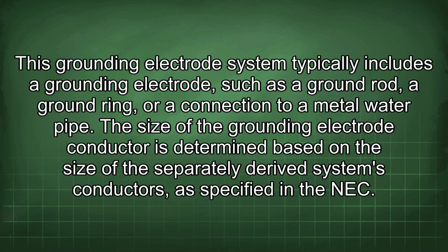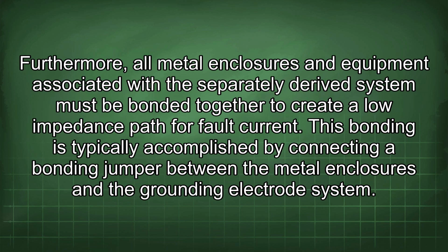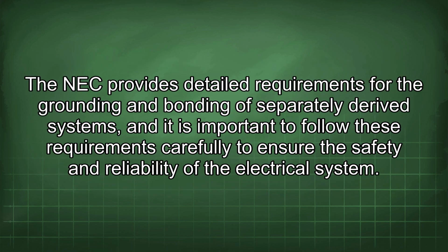The size of the grounding electrode conductor is determined based on the size of the separately derived system's conductors, as specified in the NEC. Furthermore, all metal enclosures and equipment associated with the separately derived system must be bonded together to create a low impedance path for fault current. This bonding is typically accomplished by connecting a bonding jumper between the metal enclosures and the grounding electrode system. The NEC provides detailed requirements for the grounding and bonding of separately derived systems, and it is important to follow these requirements carefully to ensure the safety and reliability of the electrical system.